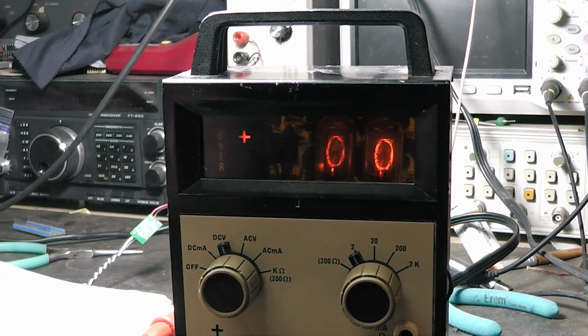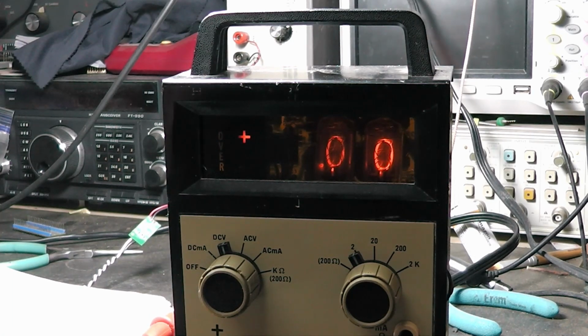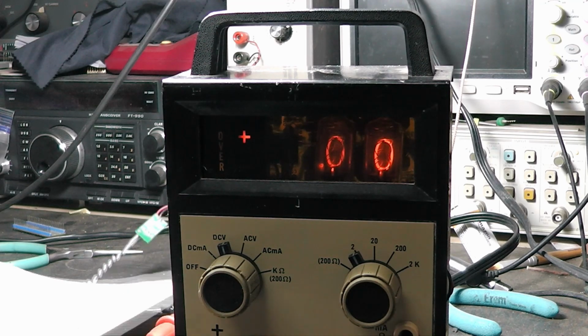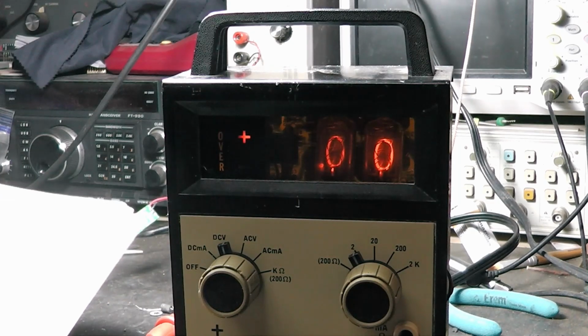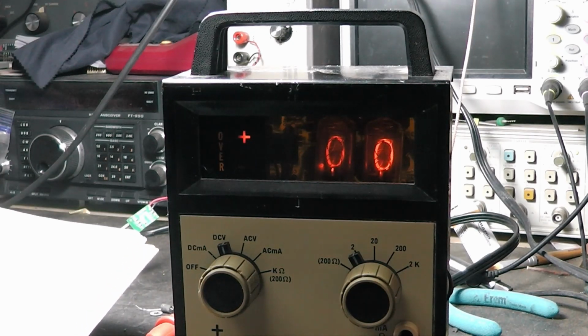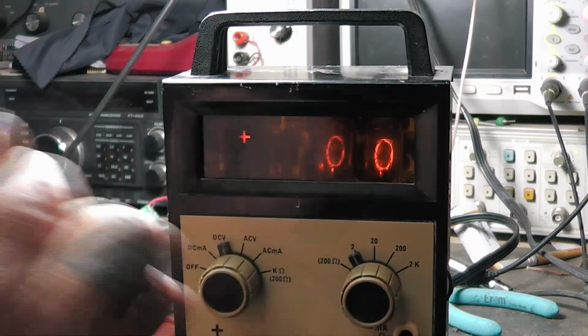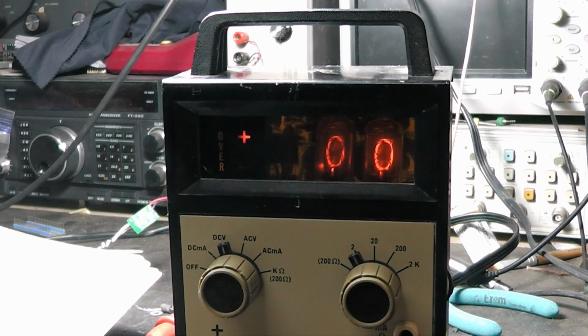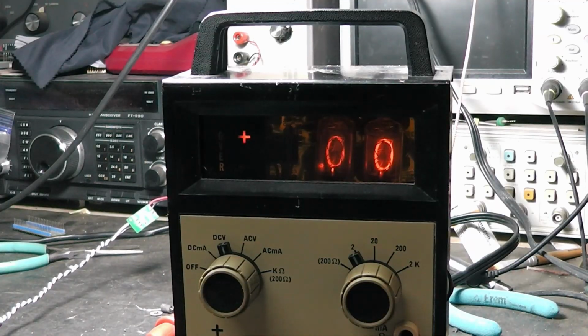It's something they've already picked at the factory when they put the resistors and everything on the test bench and made some notes. It says touch the red test lead probe tip to the DC cal control until the readout matches the value given on the calibration voltage envelope. Now this should be on 2, which, okay, it is. Observe the number on the envelope, 4 digits, and then it shows you here. Let me show you.